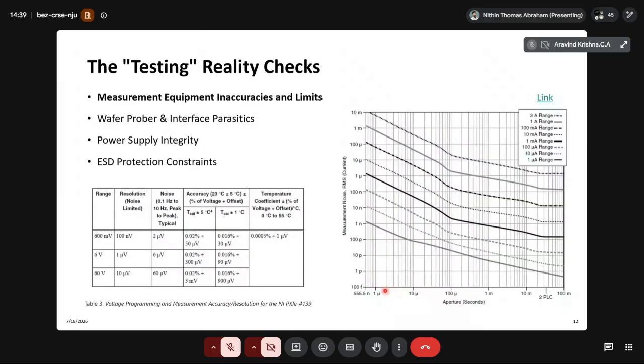Let's check the noise level. So we are measuring here in between 550 nano and 1 micro, and we have this range setting. So this is how we set the equipment to choose which range we need to measure. Let's say we set this at the 1 microampere range to measure our 1 LSB current. You can see our noise level is at 1 nanoampere, right? So that is significantly less in comparison to 1 micro. We are well and good.